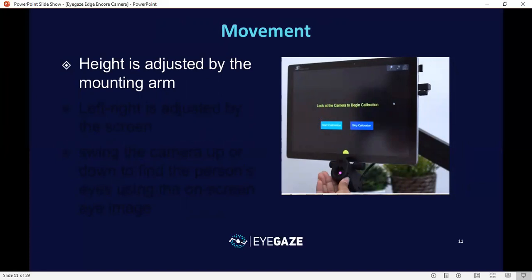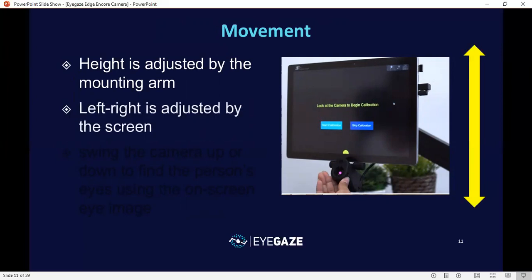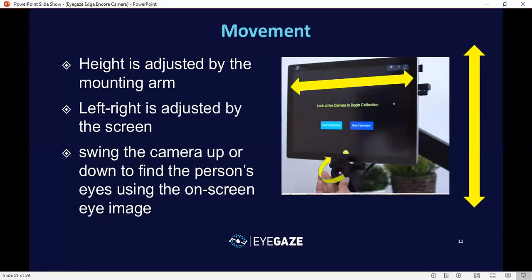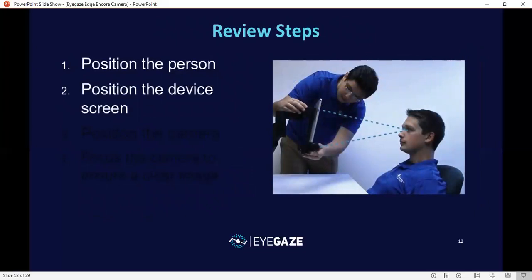If you need to move the device, remember that the height is adjusted by moving the mounting arm up and down. If you need to move it left or right, this is adjusted by grabbing the screen and moving it left or right. And then last, you'll swing the camera up or down to find the person's eyes using that on-screen eye image. These are the 3 axes of movement you can manipulate to change the position and find the right spot. So let's review these steps. First, you position the person comfortably. Then you position the device screen. Then you position the camera.